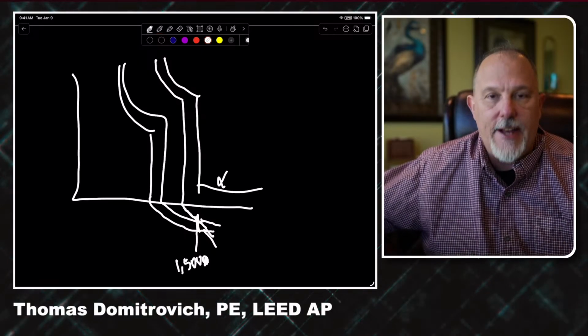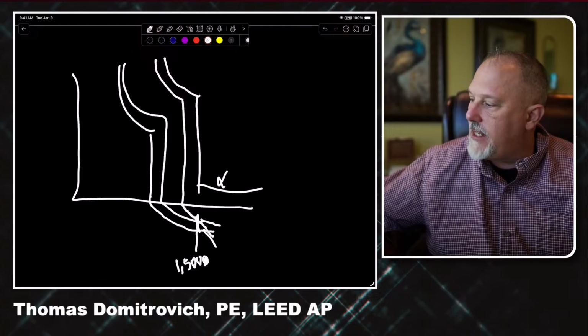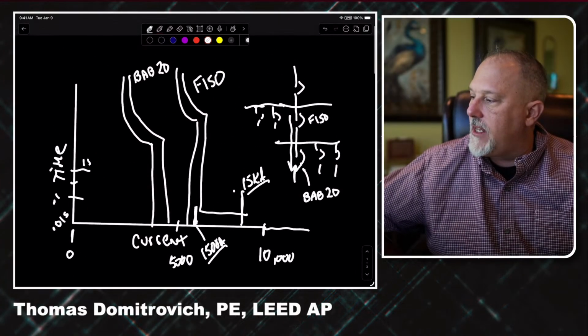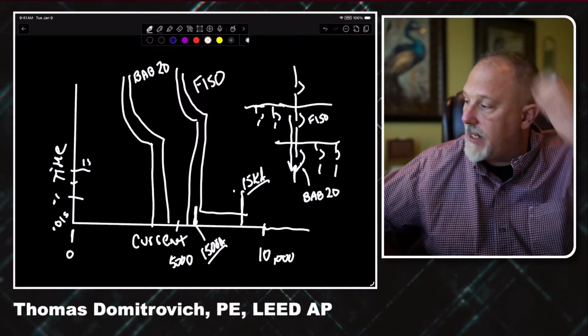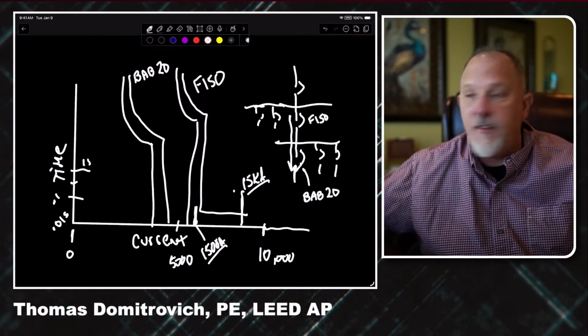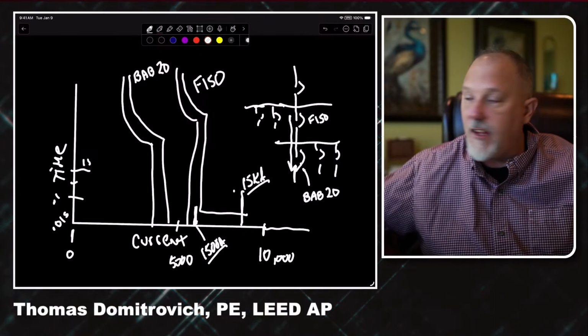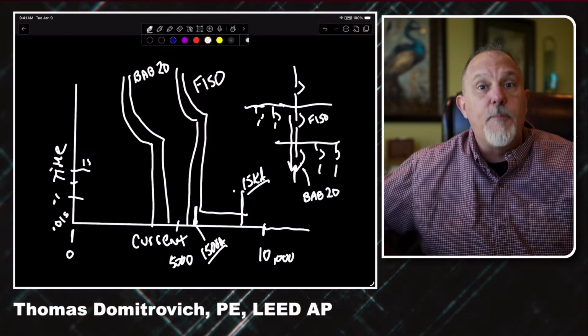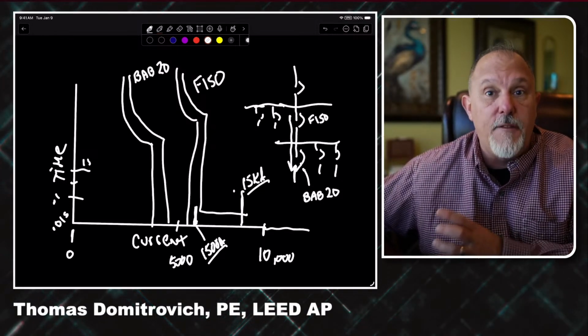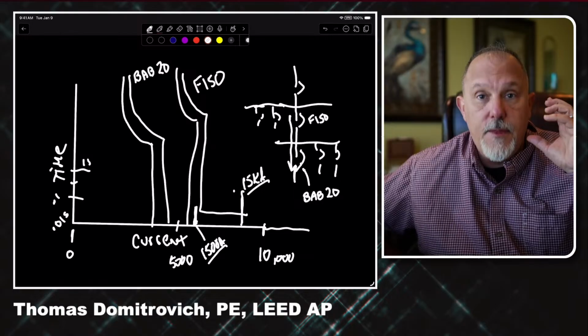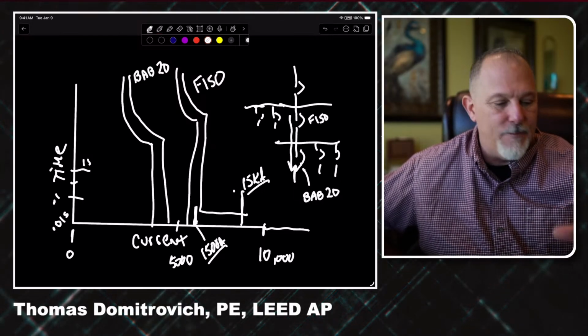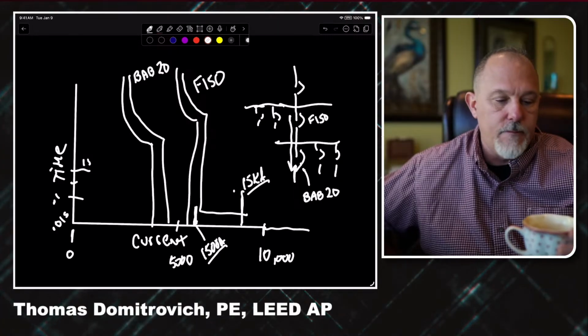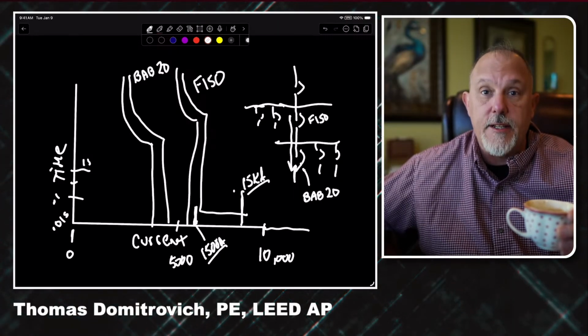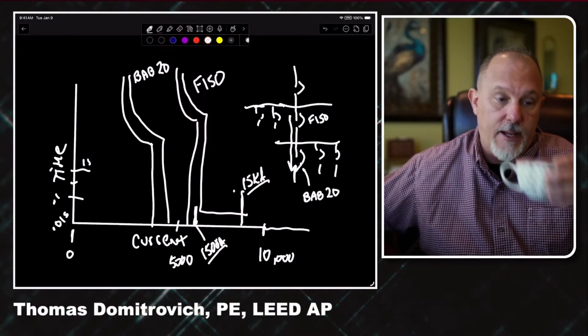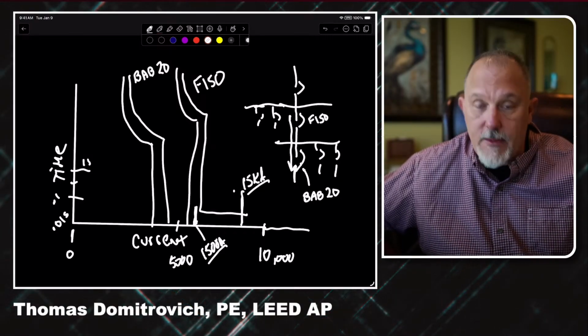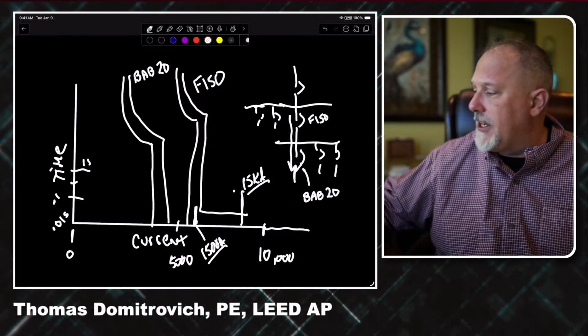And if you had any manufacturer who has a table like this for breakers like this, standard thermomagnetic breakers, like say a BAB20 equivalent from another manufacturer, an F-150 equivalent from another manufacturer, if they say that they are good up to 10,000 amps, or the interrupting rating of the overcurrent devices, they're wrong. Period. I'm just telling you, they're wrong. I would say question it and ask for the test data. And you can stick it in a lab and watch it not work as well as I could.